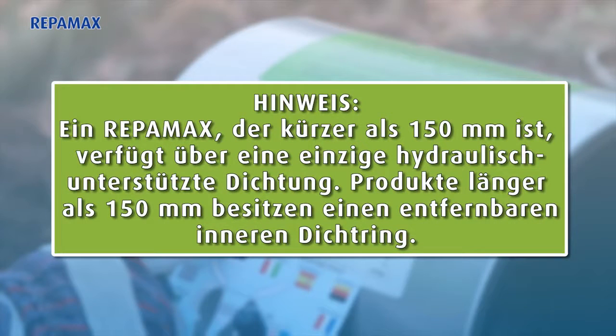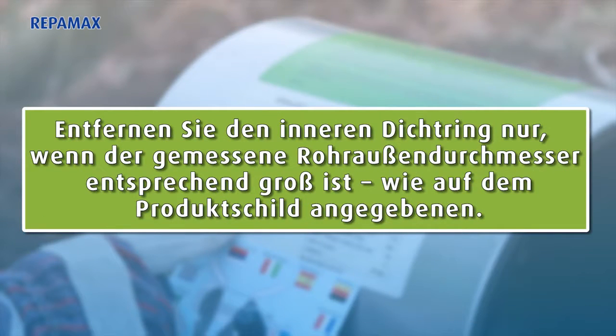Note: on a REPAMAX less than 150 millimeters, there is a single hydraulically assisted gasket. In a product larger than 150 millimeters, there is a removable inner gasket. Do not tear out the inner gasket layer unless the measured pipe diameter falls within the upper range of the product as shown on the product label.